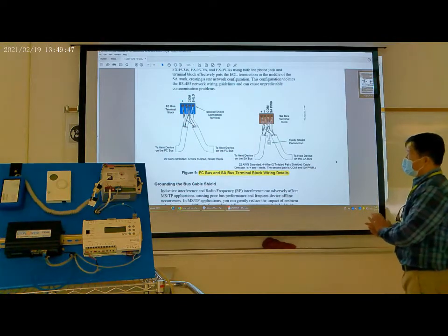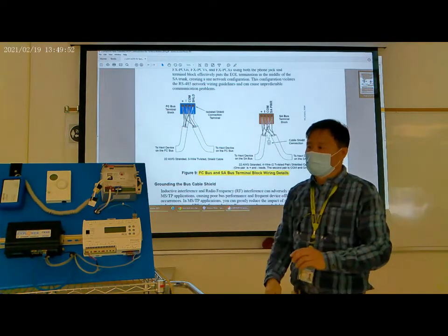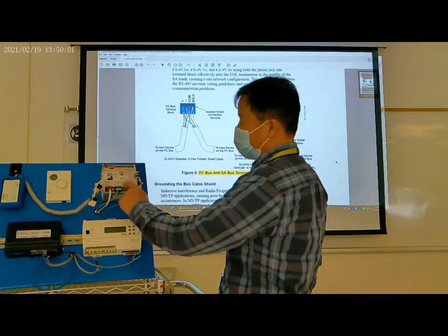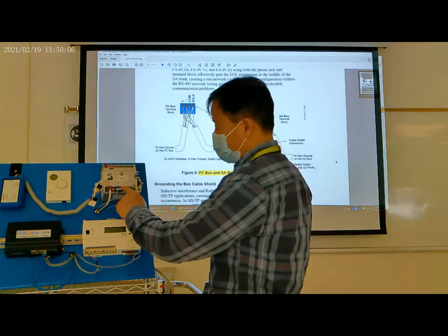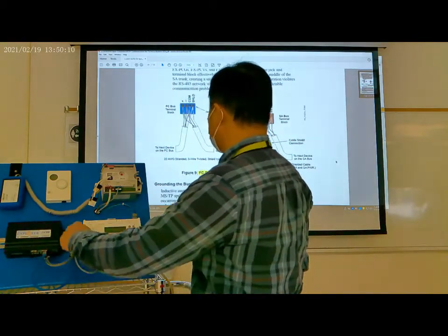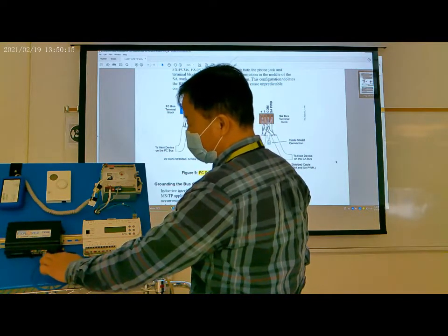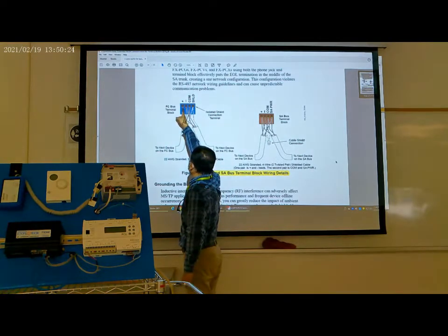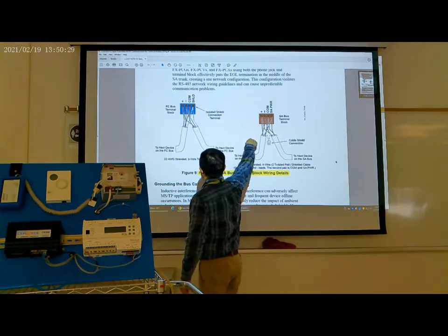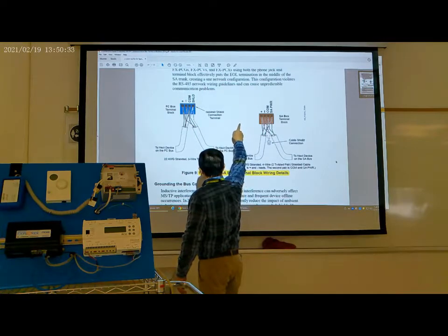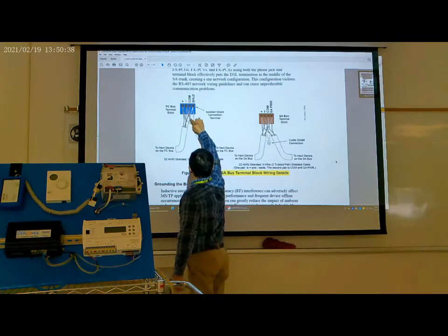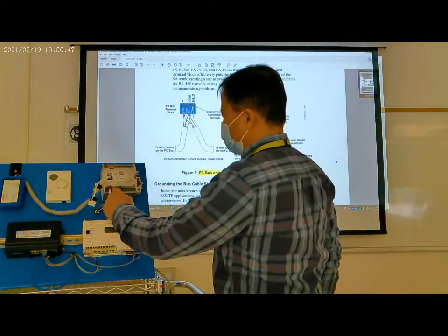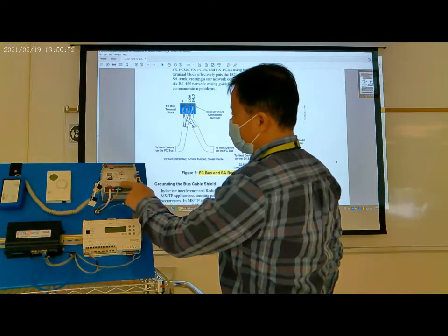Here, how to connect the FC bus: start from this controller. The cable connects to the FC bus connector here, and then from this connector, connect to the supervisory controller. The connection follows this way: positive from the controller to positive, negative to negative, and common to common. And the shield wire connects here.